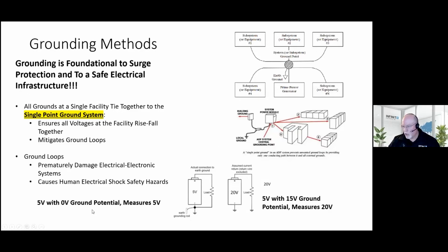If your ground potential is 0 volts like it should be, then you put your DVM in the outlet, you should measure 120 volts. But if your ground potential is, say, 50 volts, then you're going to measure 170 volts because it's relative to the ground voltage. So if there is a difference of potential from this location to that location and you don't tie those grounds together, that's what's called a ground loop. And that can cause premature equipment failure because now the equipment is suffering from 170 volts instead of 120 like it should be. And it's also a human safety issue. So if you tie those grounds together, then all voltages throughout the location rise and fall together at the same potential. And that's the point of a single point ground.